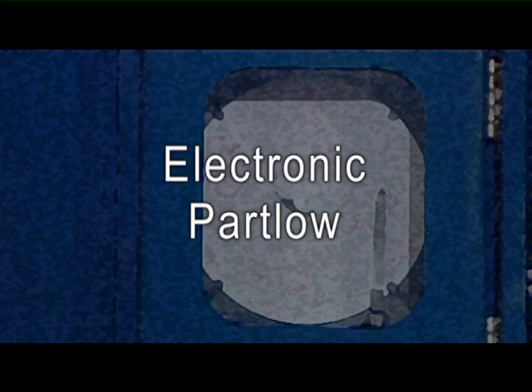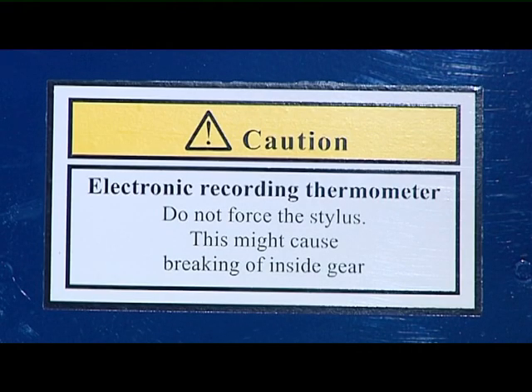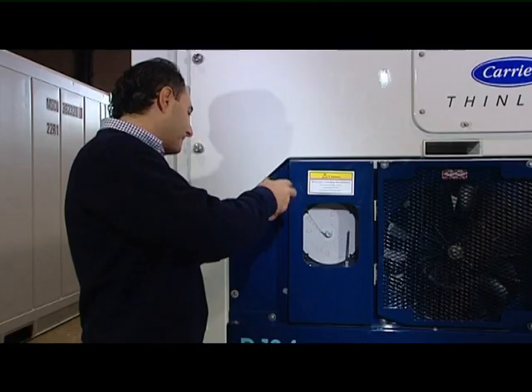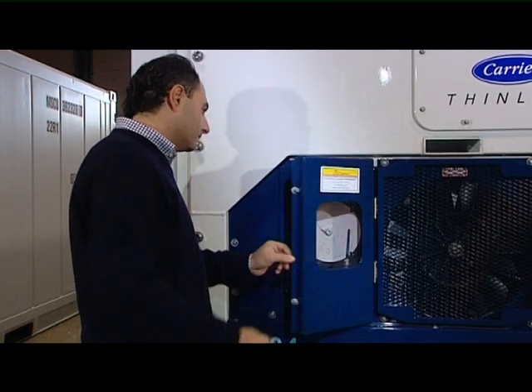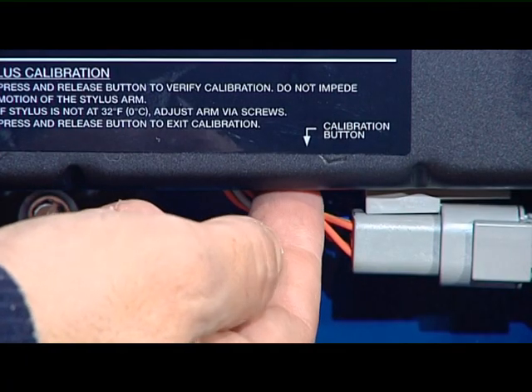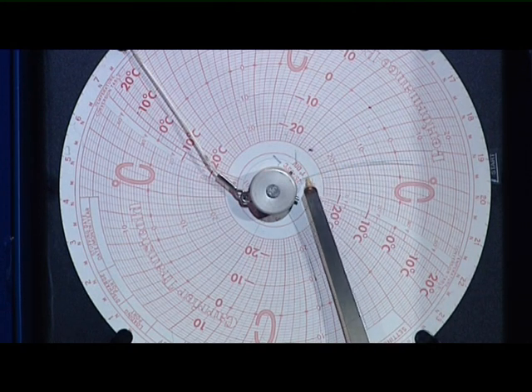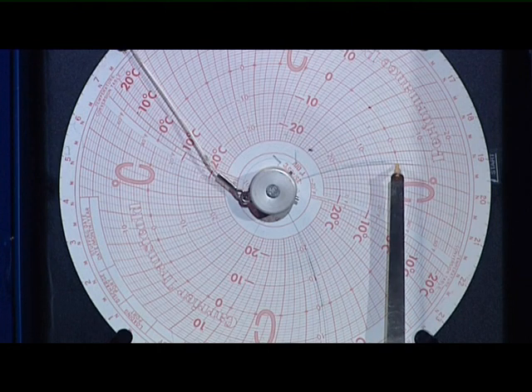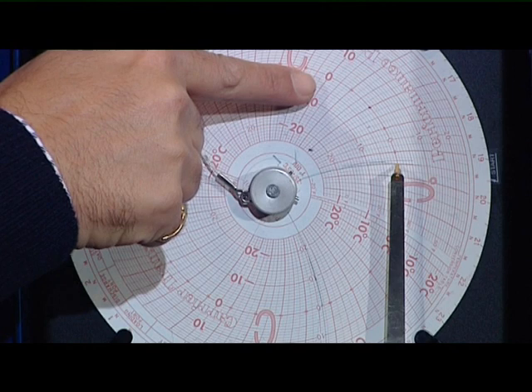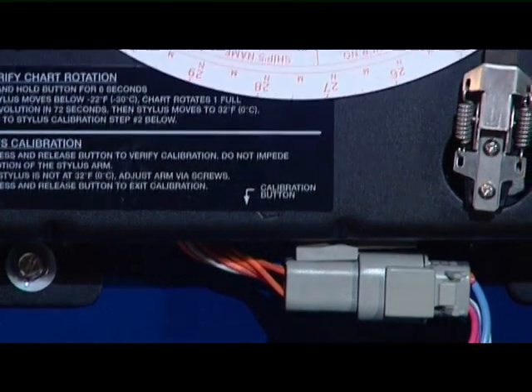Electronic Partlow: the Electronic Partlow automatically records the return or the supply air temperature depending on the set point. The recorder reads and records data from the controller — it can be compared to a printer. The recorder will stop when the power is switched off. It is possible to calibrate the electronic part low by pressing the calibration button on the bottom of the recorder. The pen will drive completely downscale, then move back to zero degrees and stop. If the pen is exactly on zero degrees, the recorder is in calibration. Press the calibration button once again and the pen will return to the correct temperature readings.